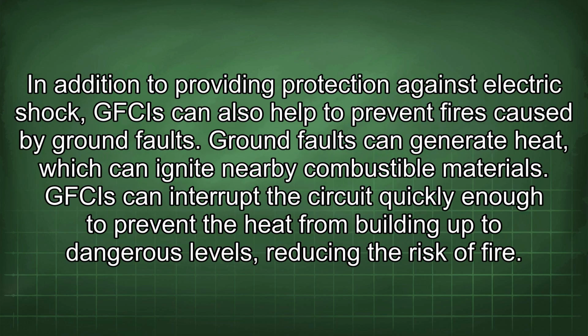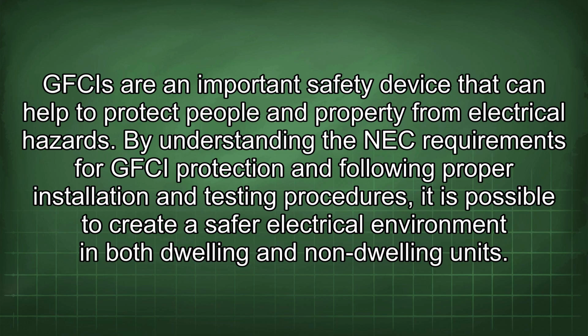In addition to providing protection against electric shock, GFCIs can also help to prevent fires caused by ground faults. Ground faults can generate heat, which can ignite nearby combustible materials. GFCIs can interrupt the circuit quickly enough to prevent the heat from building up to dangerous levels, reducing the risk of fire. GFCIs are an important safety device that can help to protect people and property from electrical hazards.